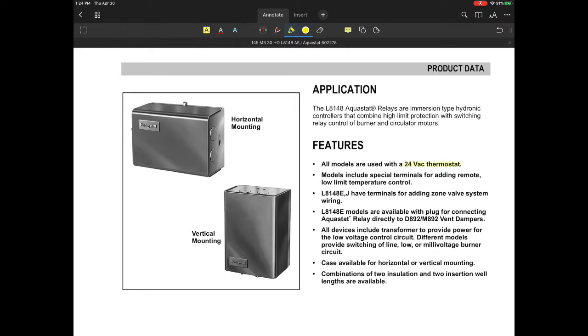The first thing that I'm going to do is switch this over to the highlighter. The first thing I want to hit up is that all of these models of Aquastats are designed to work generally with a 24 volt thermostat, is what they're saying. And I'll get more into what we specifically mean by that a little bit later. Now, in most applications, we really don't wire a thermostat directly to the Aquastat. So it's a little bit of a confusing statement that's in there. All models are used with a 24 volt thermostat. I think they simply mean that they have a power supply that allows you to work with a 24 volt system.